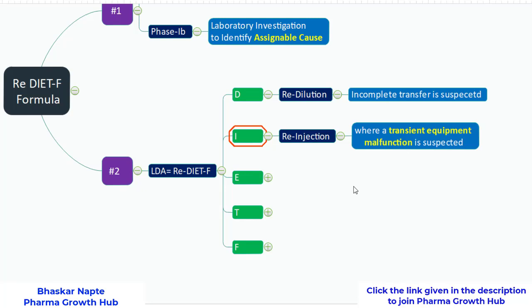In case you found that the HPLC vial was not properly capped, the septa was slipped, and because of that probably the injection did not happen appropriately, then the re-injection becomes the experiment which may help you in understanding whether the septa was appropriately kept or not.